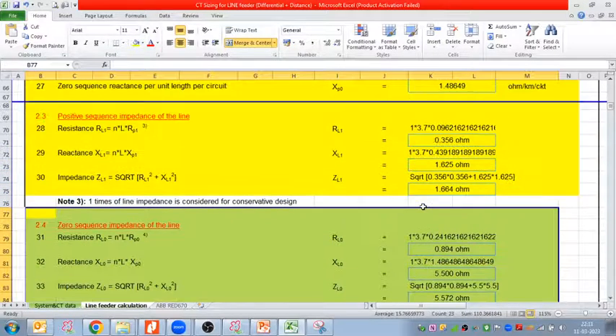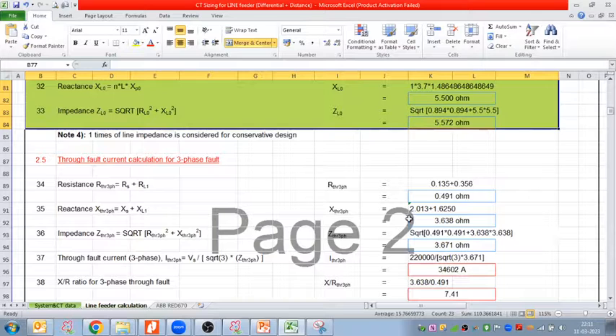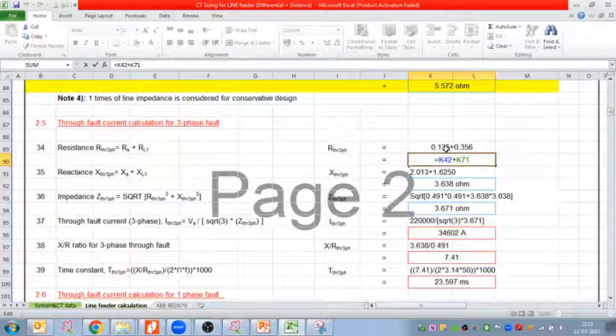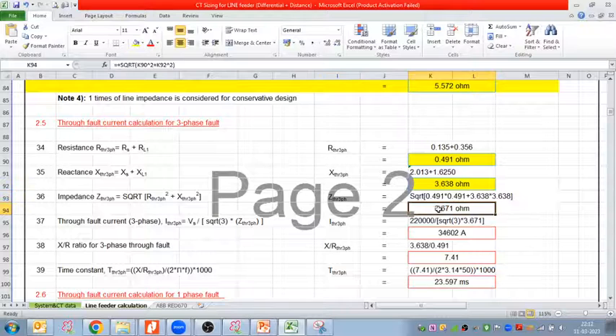So now coming to the through fault current calculation. Again, resistance till my protected point, so Rs plus RL1. This we calculated: 0.135 is my source resistance plus 0.356 was my line conductor resistance. So the total resistance I'm getting is 0.491. Similarly, the net reactance I'm getting till the fault location is 3.638. So with R and X, we can find the impedance Z, which is the square root of R square plus X square. 3.67 ohm is the value we are getting here.